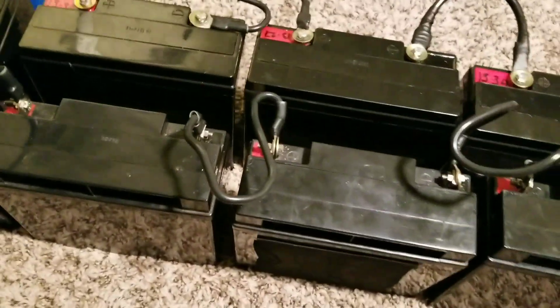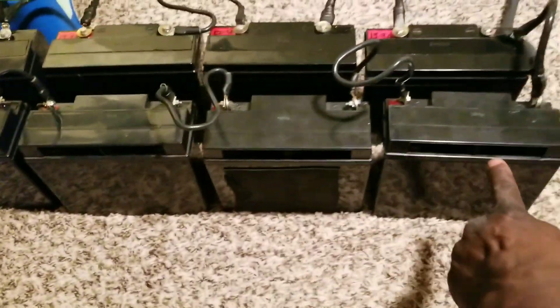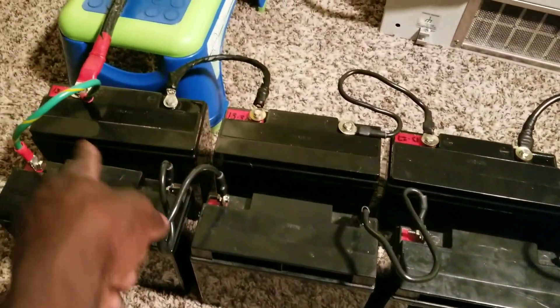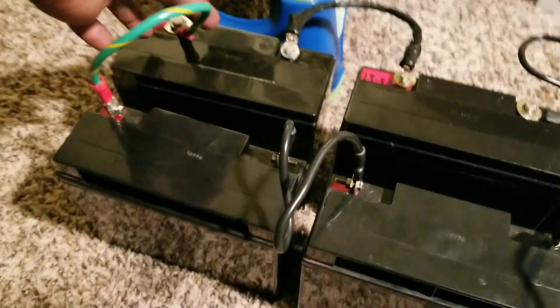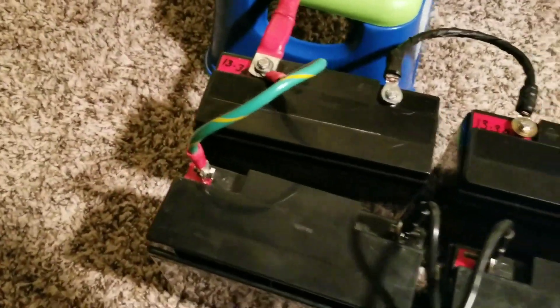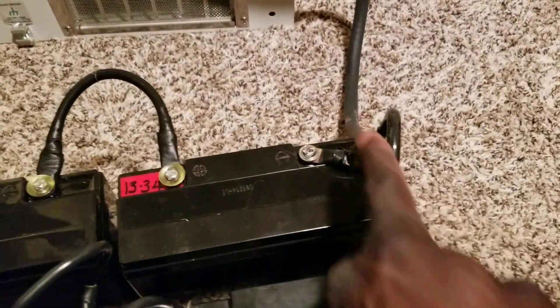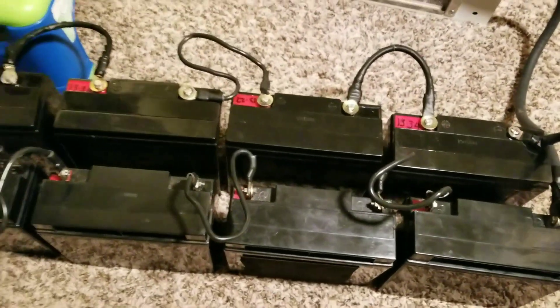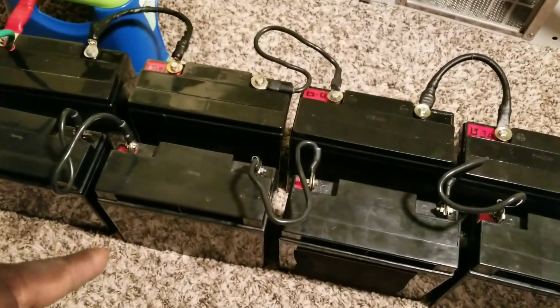With another 22 amp hour string in series and then paralleled together, you can see one string runs from here all the way here — that gives you 48 volts. Then parallel here: positive to positive and negative to negative. These are just a simple setup for the test; it's not going to be wired like this permanently.